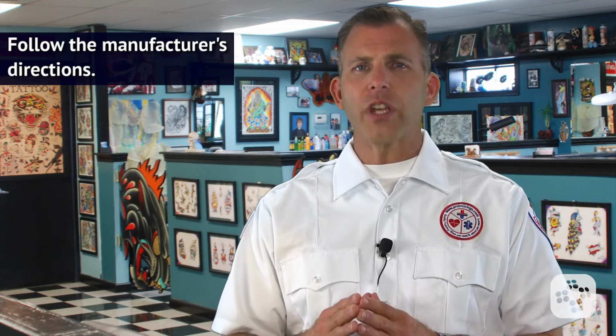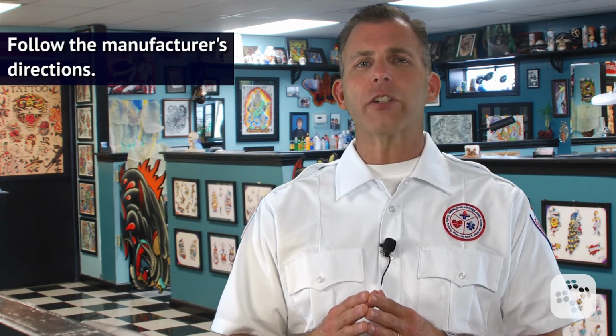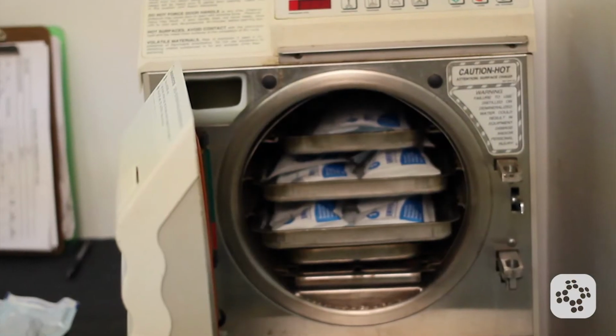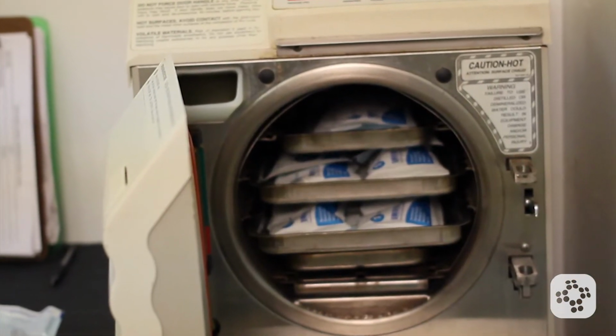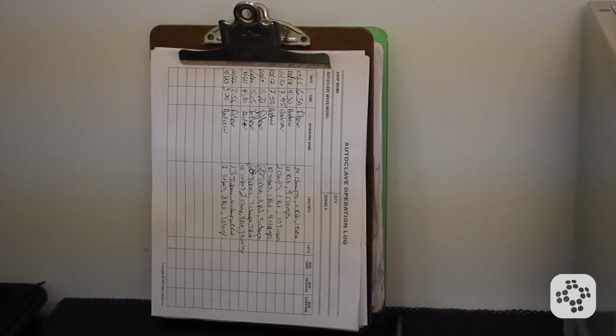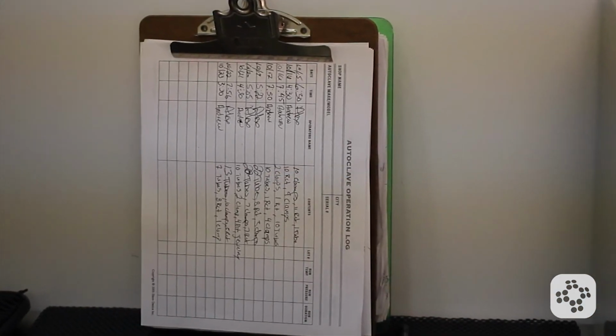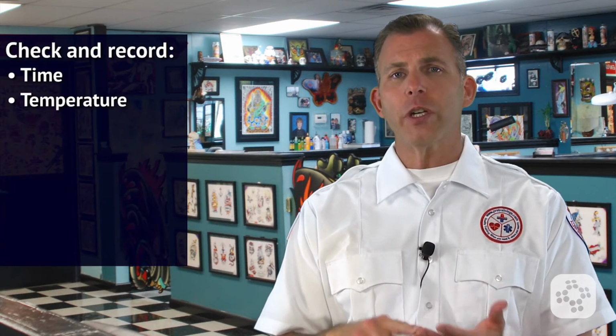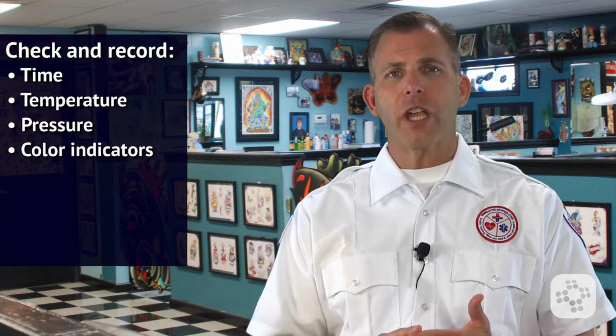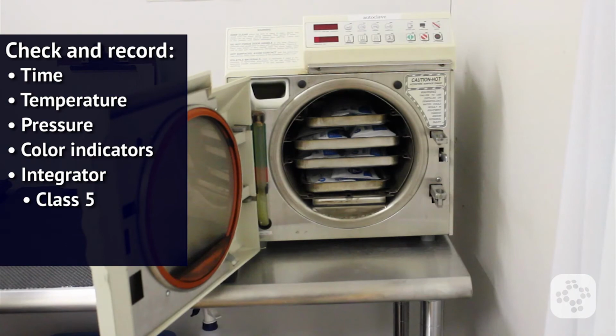For proper sterilization, an autoclave must be monitored and sterilization logs need to be kept. Monitoring includes spore testing monthly, or more frequently if required by your local health department, and checking and recording the following. We need to check the time, temperature, and pressure readings, color indicators on each package, and the integrator in each load. At minimum, a Class 5 integrator must be used in each load.